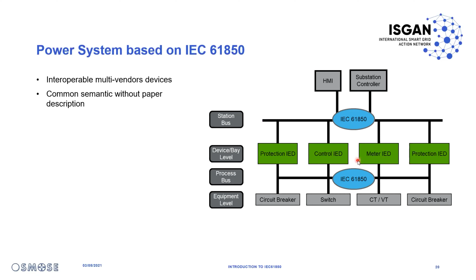IEC61850 has brought another brick on top of that, which was a common semantic in an electronic format, allowing machine-to-machine exchanges with less risk of misinterpreting data between different devices. This allows increased efficiency in system setup by using one common interface and reducing risk and cost of deployment and maintenance phases of the system.